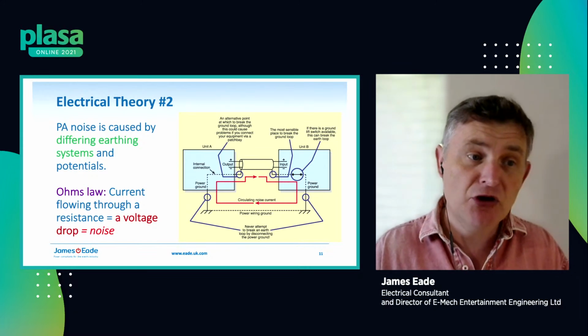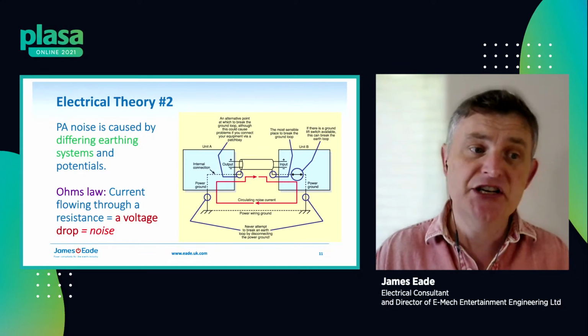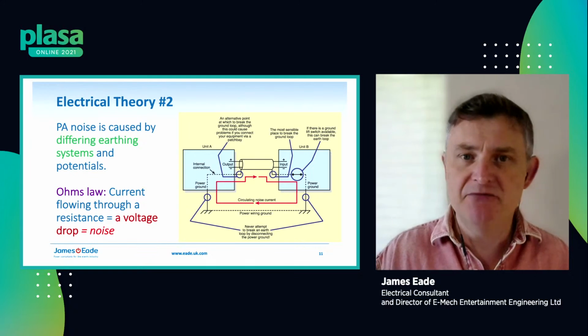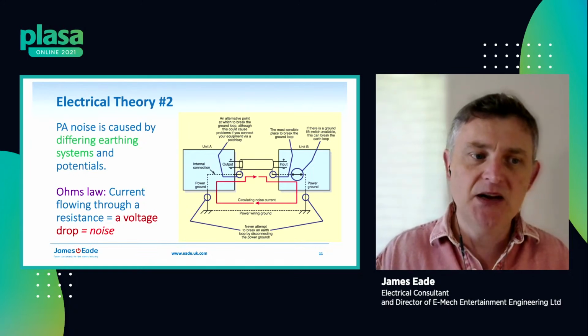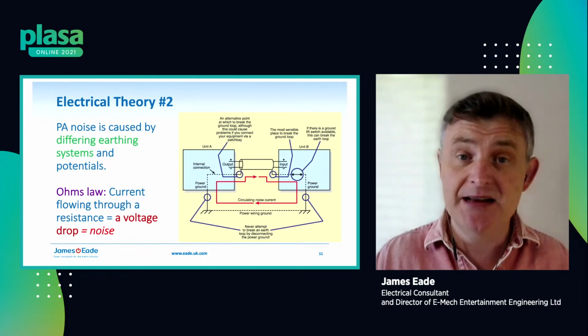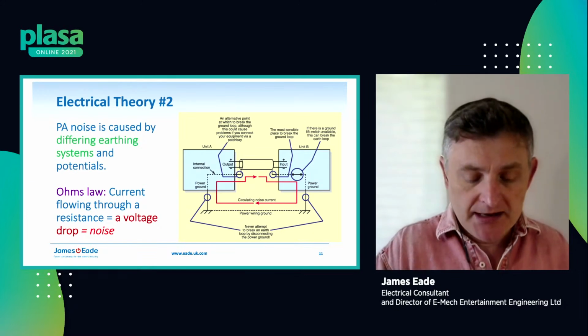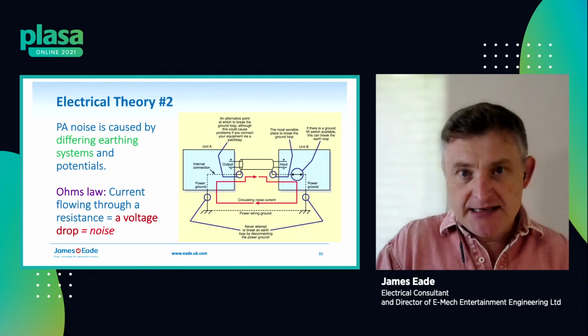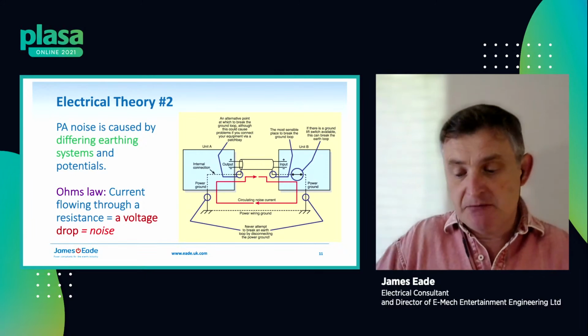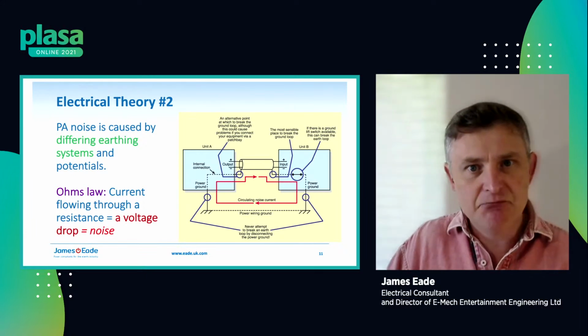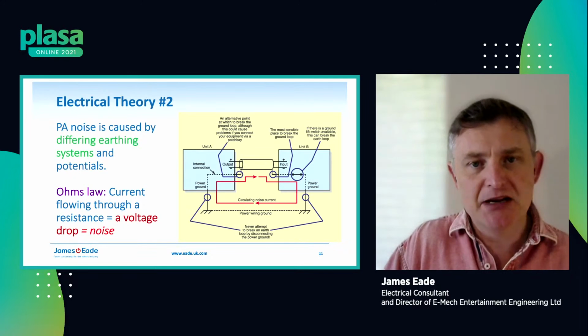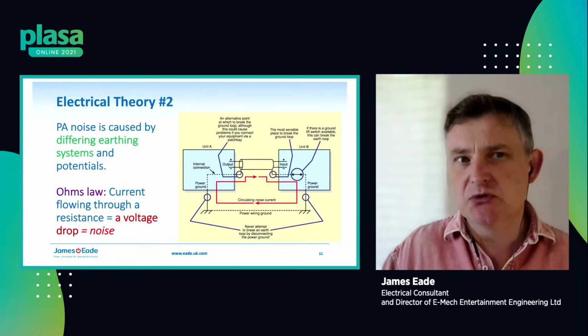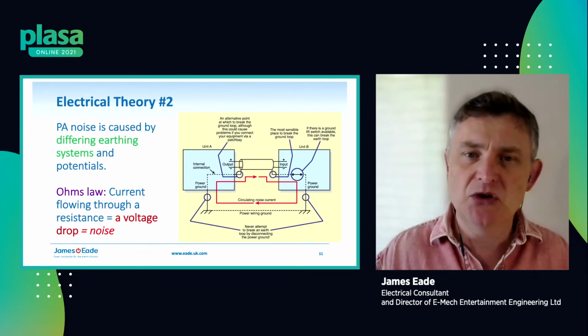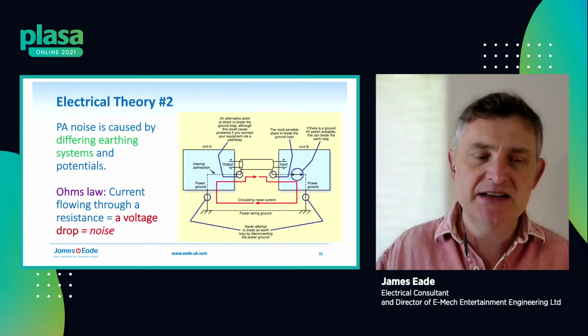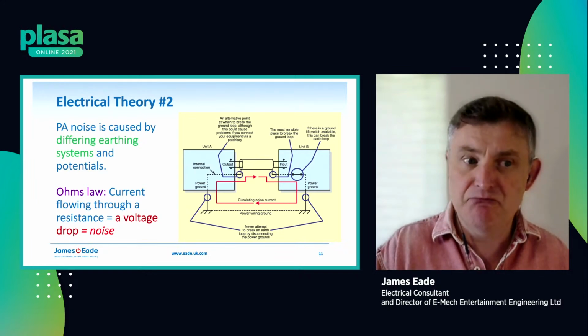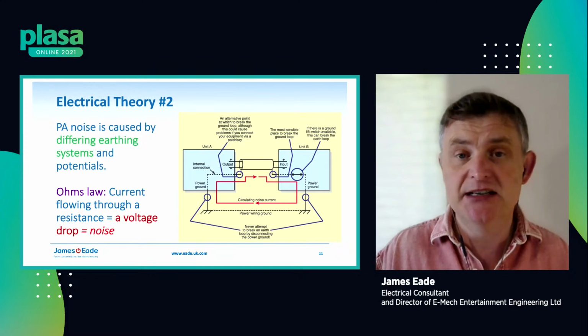On an allied one from Craig, is it still good practice to have separation between power and signal, i.e. video and audio cables? Or is this less important with improved cable insulation? Well, it's still recommended that you keep separation, because you can still get radiated magnetic interference emanating from cables being induced on signal cables. Although, given the quality of balanced lines and receivers these days, it's much reduced compared to what it used to be.